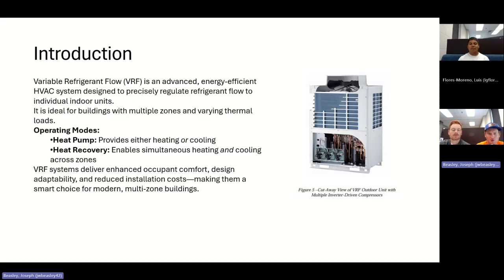Variable Refrigerant Flow is a system that is advanced and energy efficient, and it's designed to precisely regulate refrigerant flow to individual indoor units. This is good for buildings like schools or hotels where there are multiple zones and each zone requires a different temperature control. The operating modes are heat pumps and heat recovery systems. And the heat recovery system takes excess waste heat from one zone and uses it for another, making it a very efficient way to heat or cool the building.